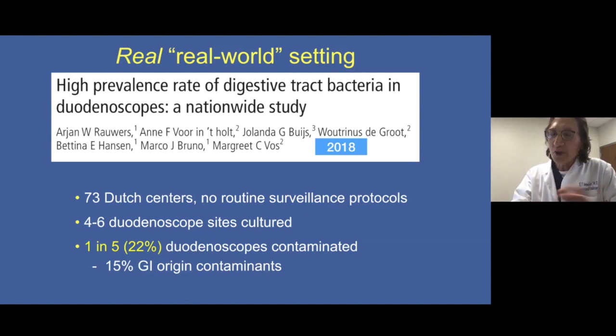So you heard about double reprocessing, and probably about 50% of the centers do this. We actually are not doing the double reprocessing, but we're taking other measures to address the contamination that we can discuss later on. But this is a great study that Doug Rex did at Indiana University. They cultured 592 duodenoscopes that had undergone double reprocessing, right? So you do the high-level disinfection twice. And what they found was that the contamination rate was almost the same as what was reported in the post-market survey that the FDA conducted, 9.4%.